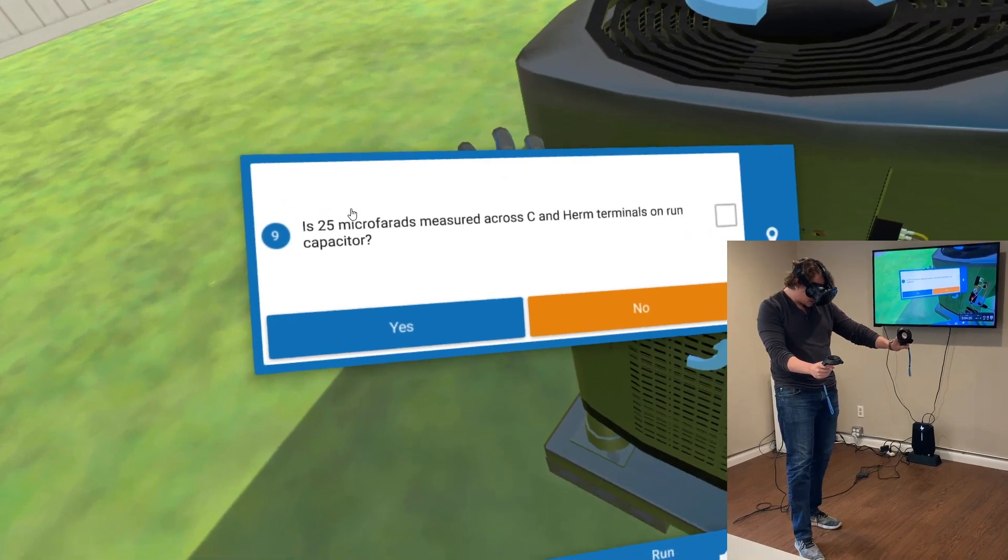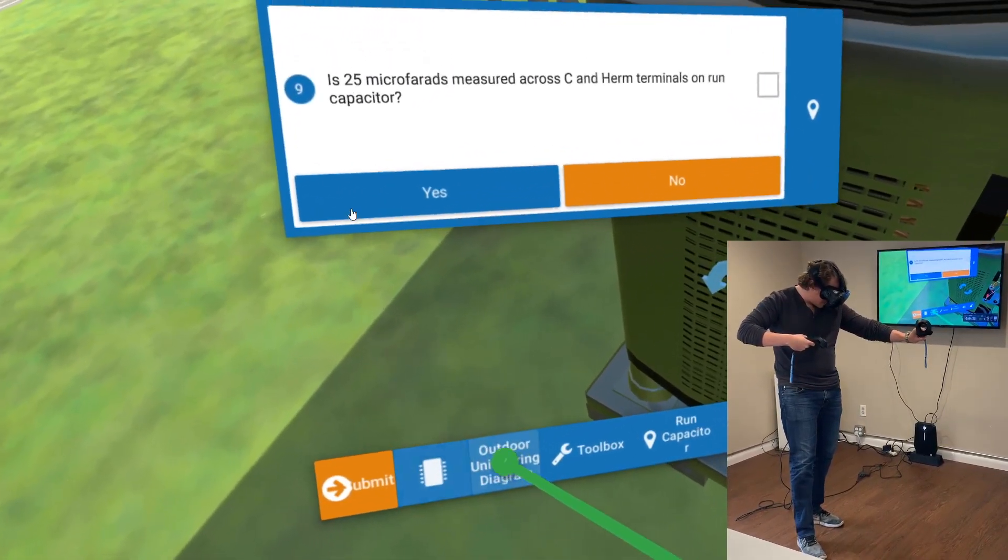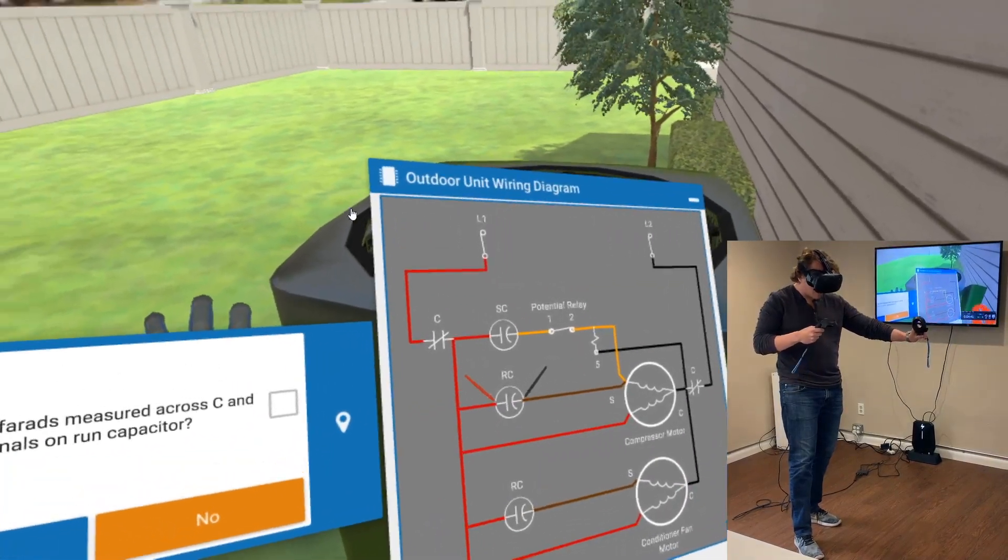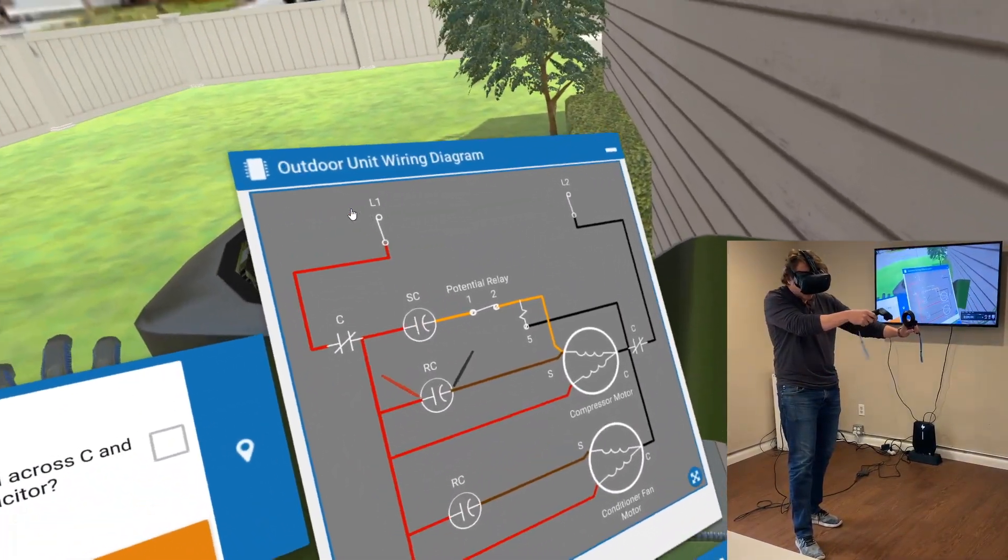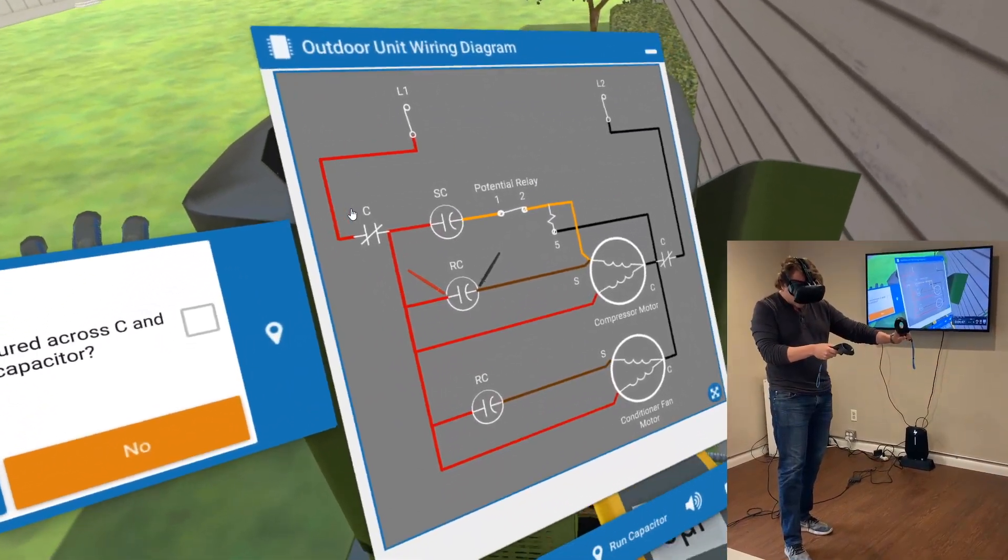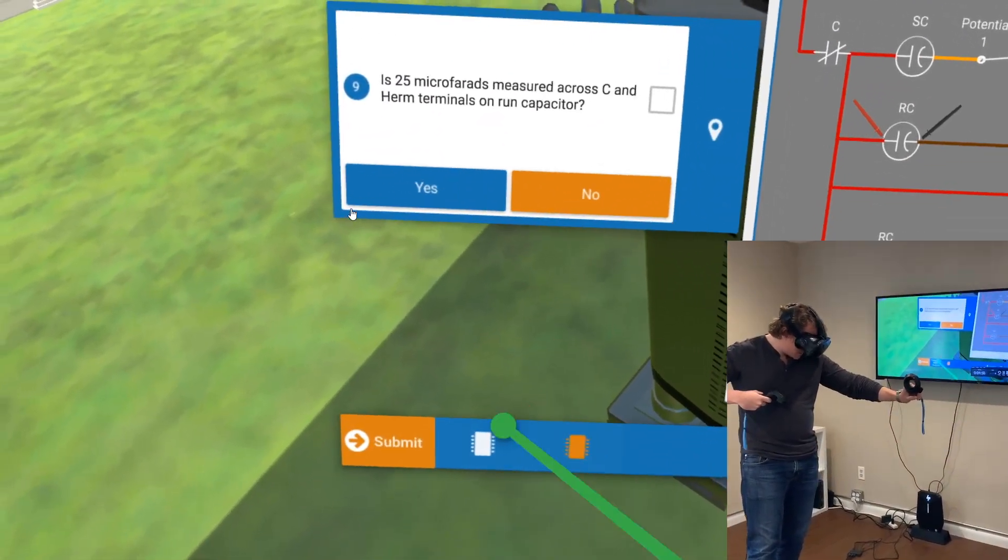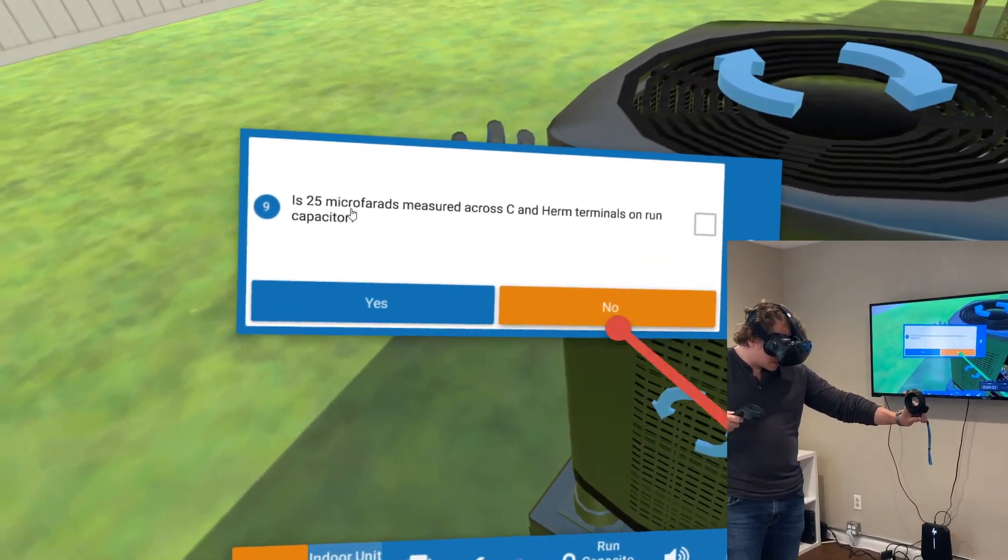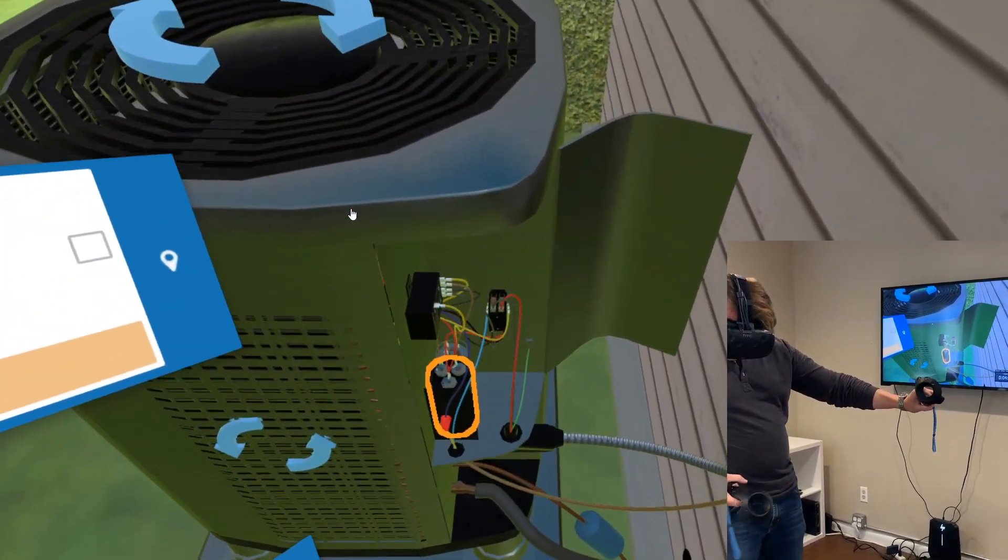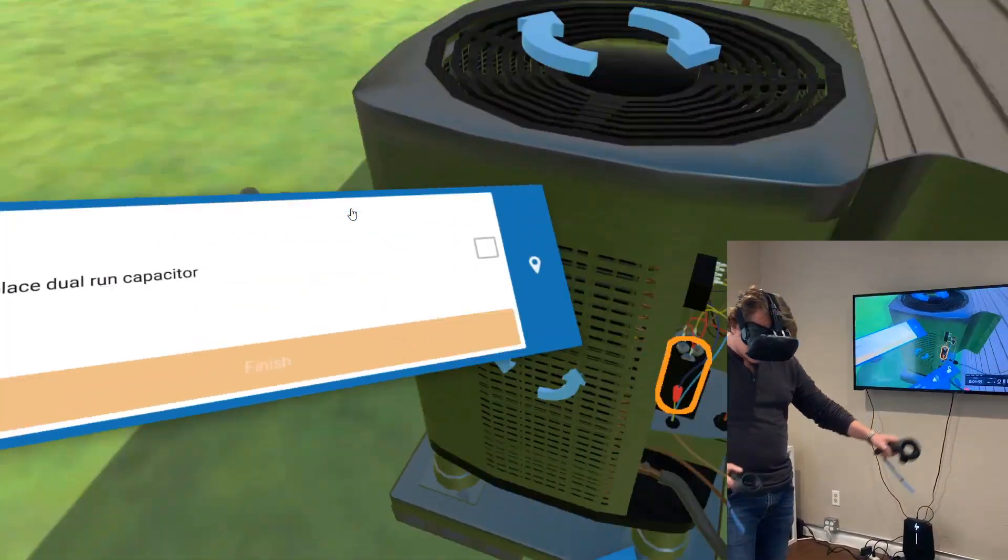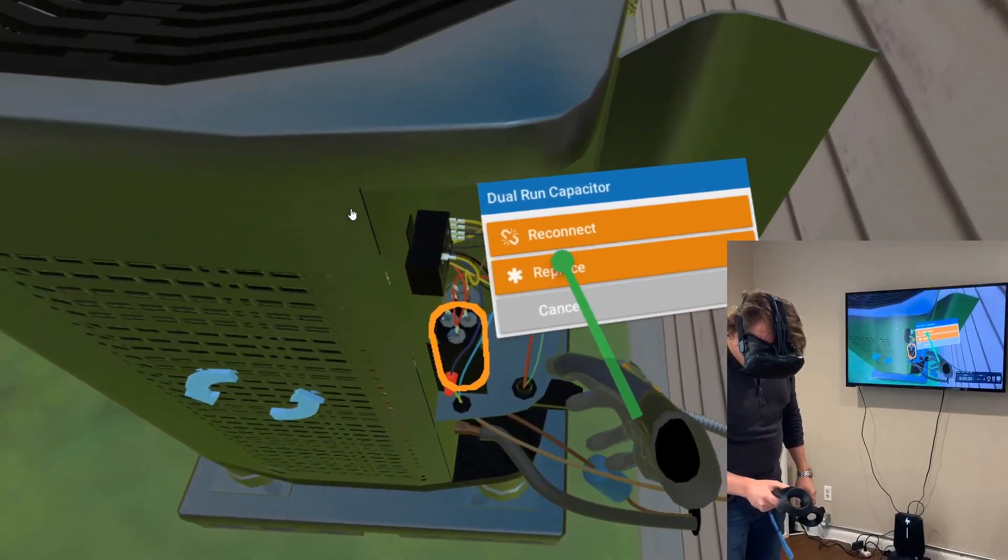I'm going to throw on here the visual outdoor wiring diagram. The disconnect's been tossed so there's no visual showing electricity, but you can actually still see where our wiring diagrams are. I'm going to close that and start to replace the dual run capacitor because we're obviously confident today it's a run capacitor issue. Now I'm going to work on replacing it.